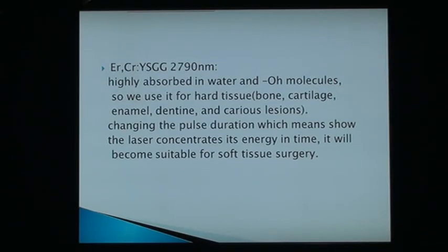And the second one, we have erbium chromium YSGG. Its wavelength is 2790 nanometers. Also, it is highly absorbed in water and OH molecules, so we use it for hard tissue, bone, cartilage, enamel, dentine, and caries lesions. Changing the pulse duration means the laser concentrates its energy in time, and it becomes suitable for soft tissue surgery.